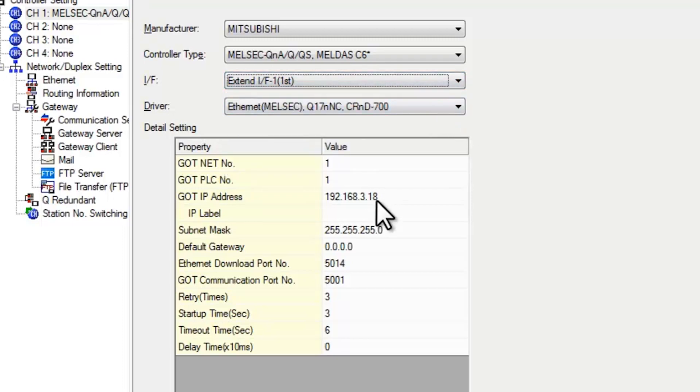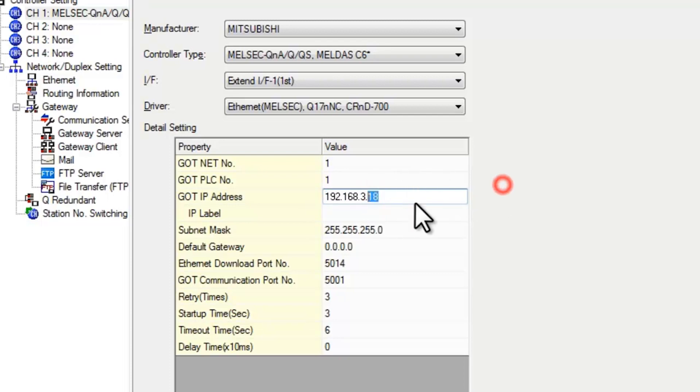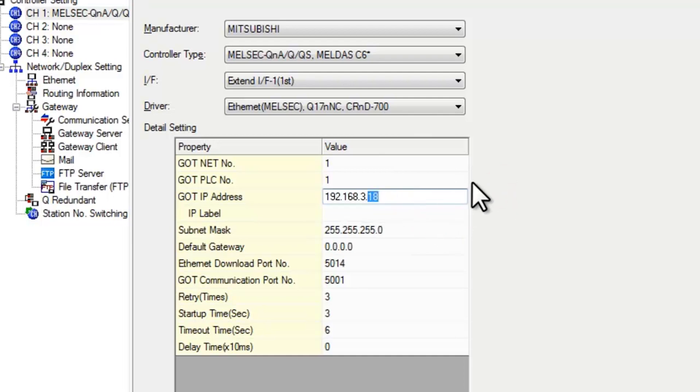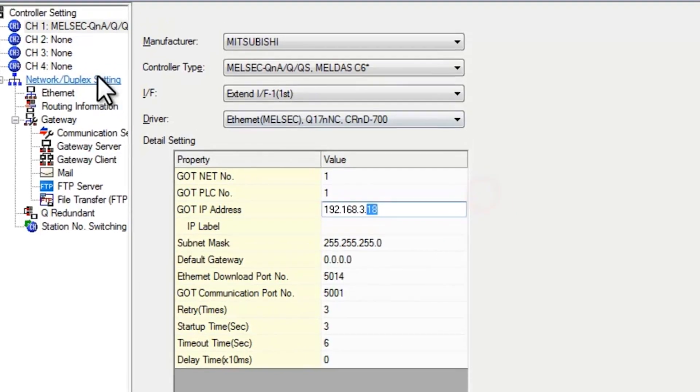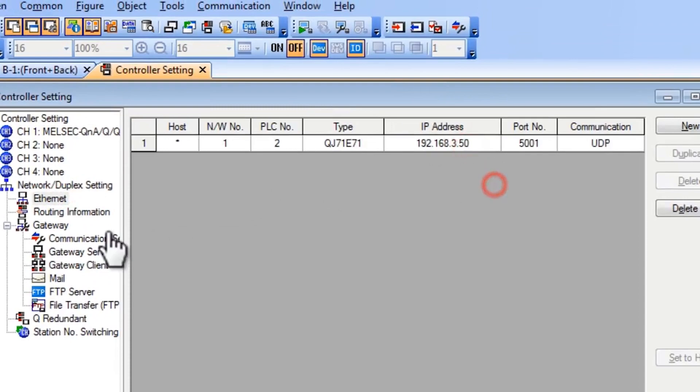And your IP address. Everything needs to match the PLC all the way up into the last digits here. The 18 needs to be different from the PLC. So again, here 18 is different from 50. Make sure those are different.